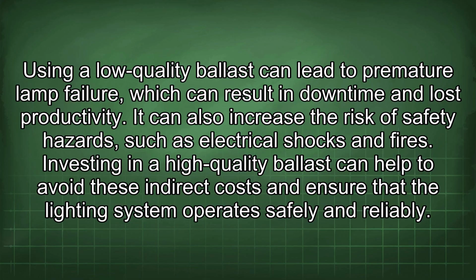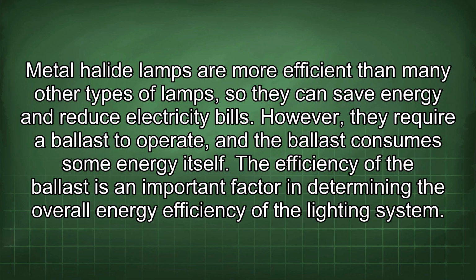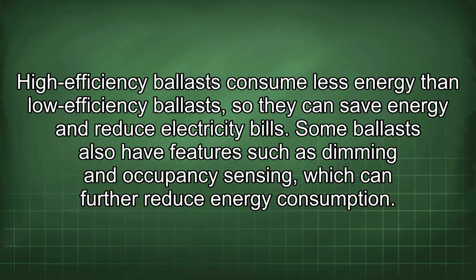Metal halide lamps are more efficient than many other types of lamps, so they can save energy and reduce electricity bills. However, they require a ballast to operate, and the ballast consumes some energy itself. The efficiency of the ballast is an important factor in determining the overall energy efficiency of the lighting system. High-efficiency ballasts consume less energy than low-efficiency ballasts, so they can save energy and reduce electricity bills. Some ballasts also have features such as dimming and occupancy sensing, which can further reduce energy consumption.